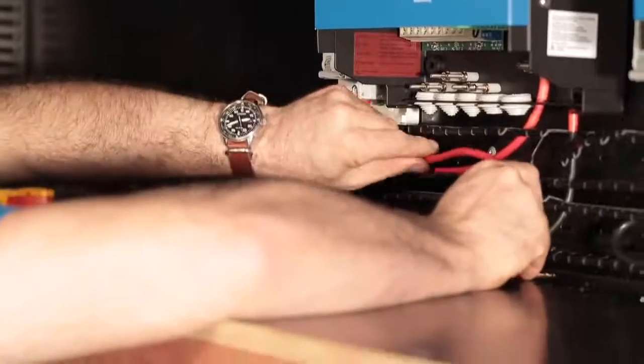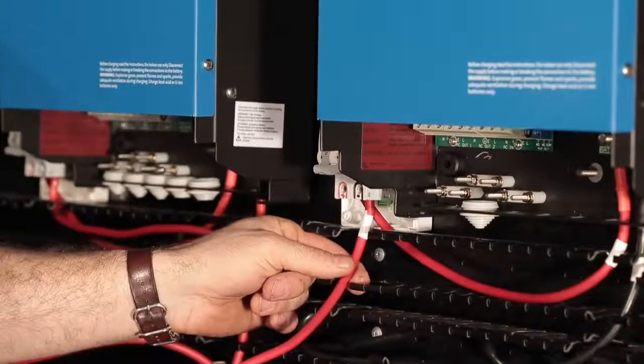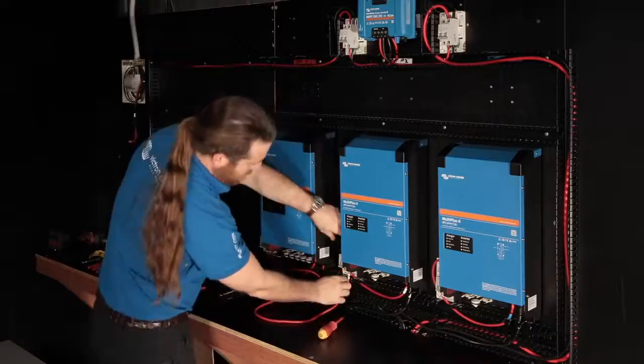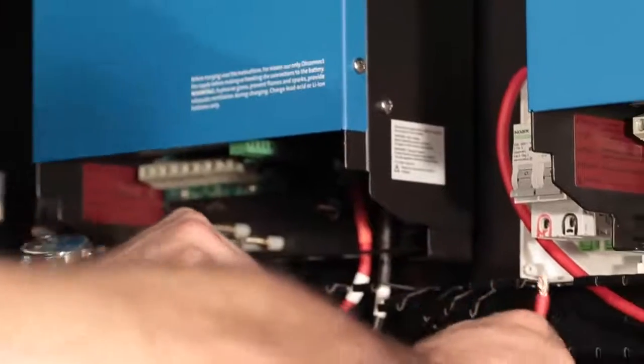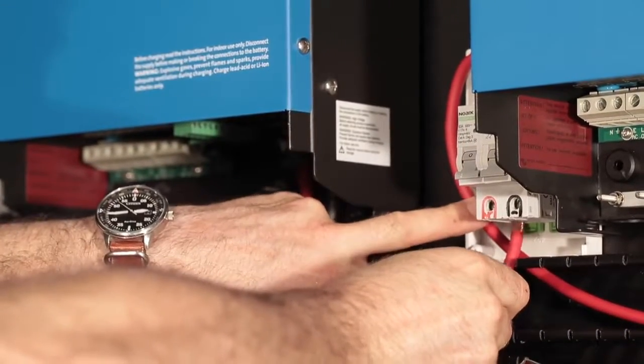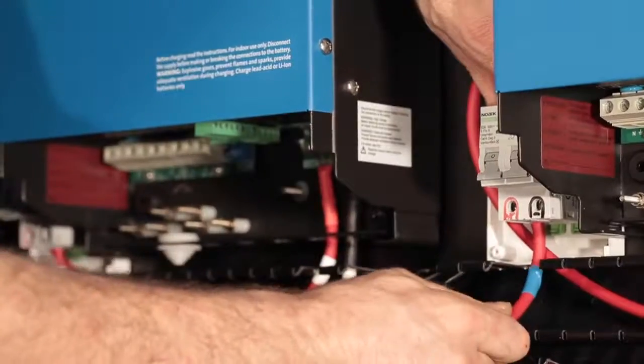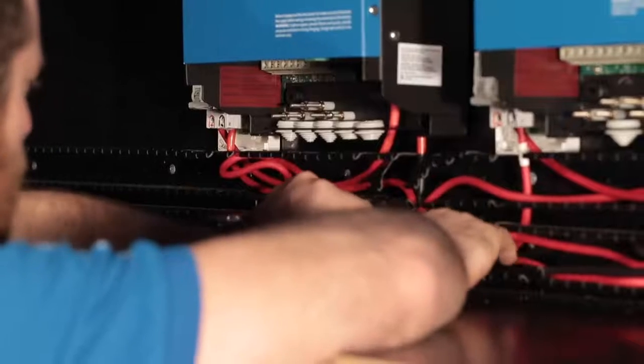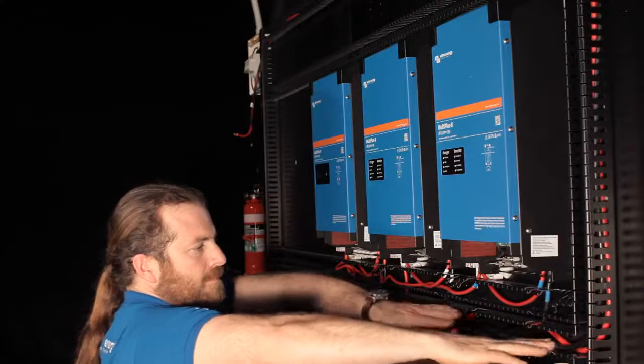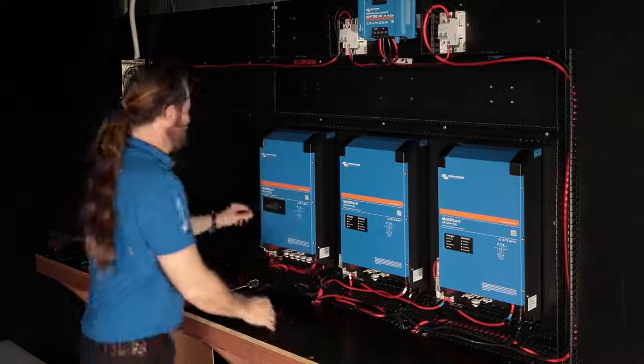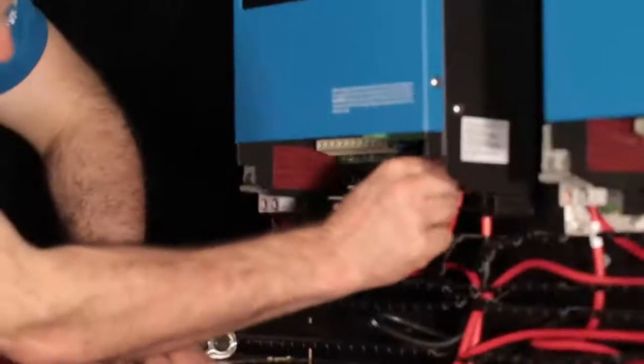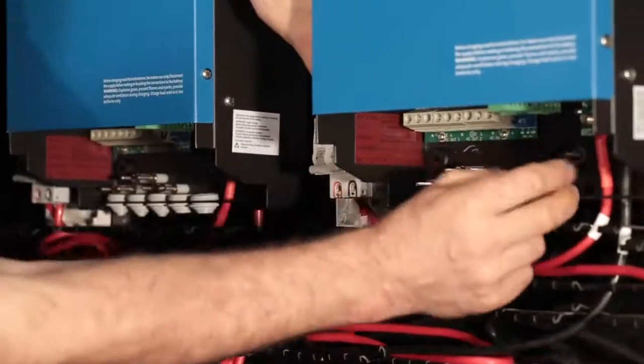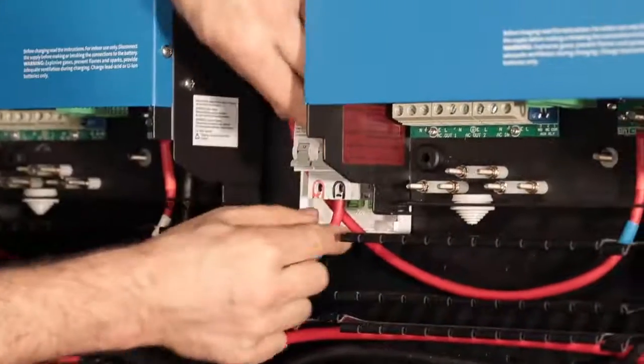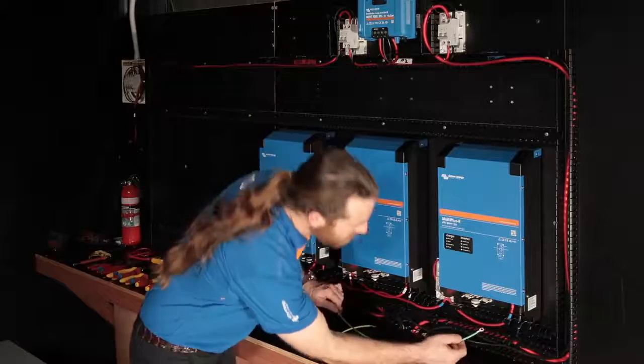As we cut the cable, we'll now be making the connection from the bottom of the isolator to the battery cable, which will run down to the DC bus. Again, make sure these cables have no stray wires, and check them for firmness. Once all the positive cables are neatly connected and run through the trunk or through a back wiring system, we can double check all the connections, make sure everything's secure and looks good. These cables can run a high current, so it's really important these connections are right.